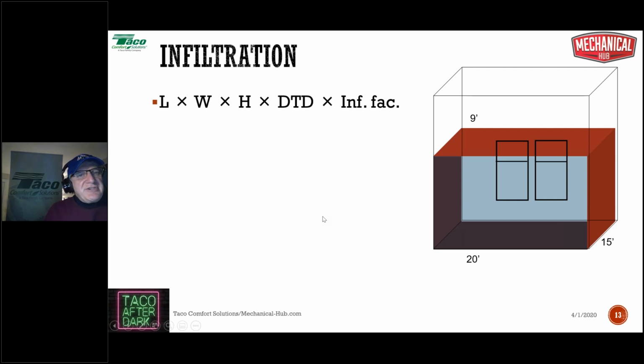Here is your infiltration heat loss math formula, and it's all multiplication. This is one of the ways math is really cool. When you're multiplying, you just do it in a string, it doesn't matter what order. In this case, length times width times height times your design temperature difference times your infiltration factor will give you your infiltration BTU load. So let's fill in the blanks.